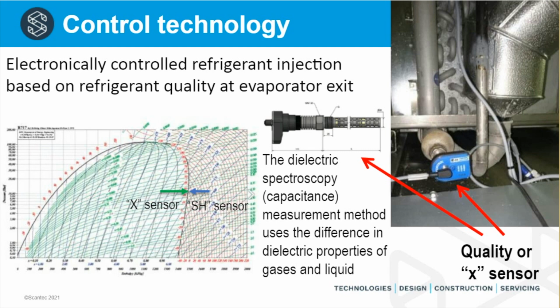It's very important that the sensor is not submerged into liquid. If it gets submerged into liquid, it has a tendency to send a signal that the control system can't read. In those situations, we switch to superheat control until the quality sensor has found its way again, and then we switch back to quality control of the injection.